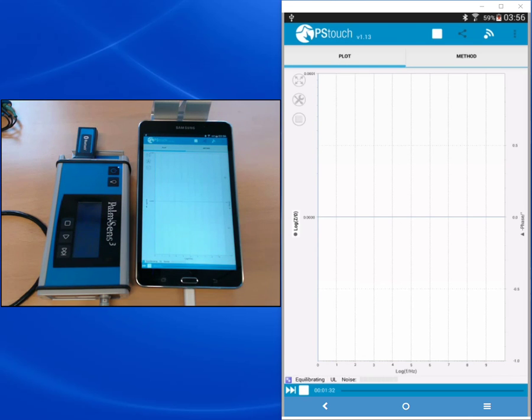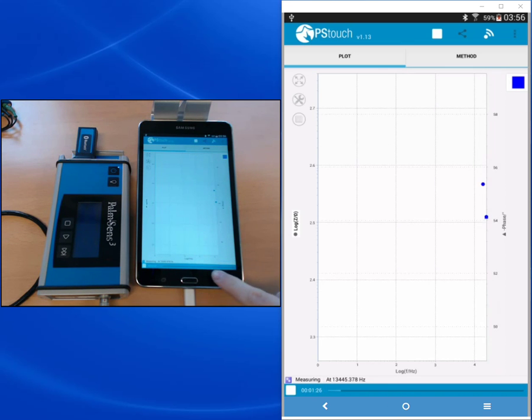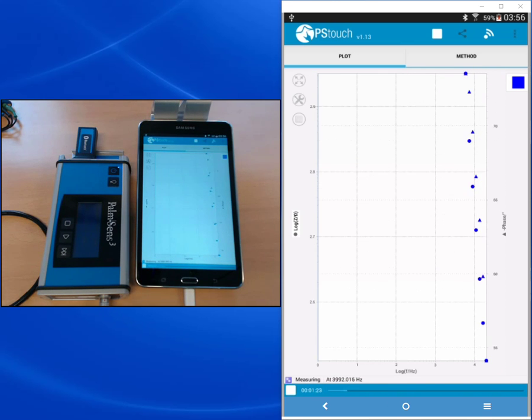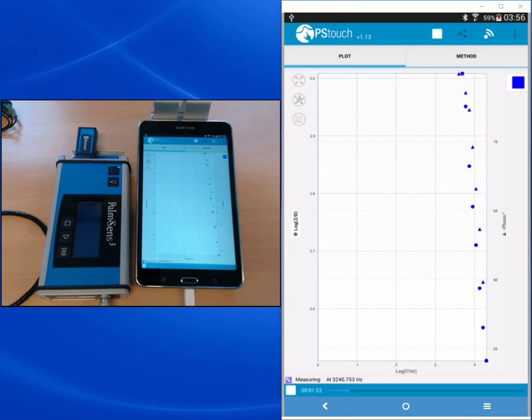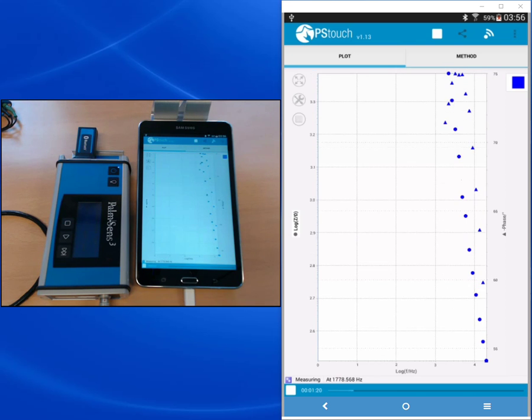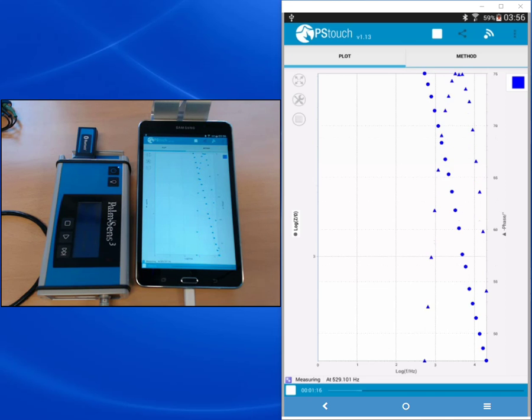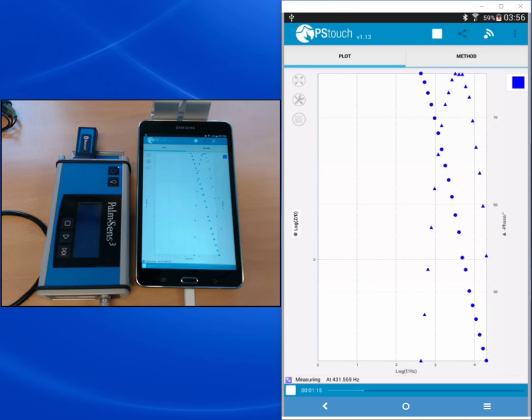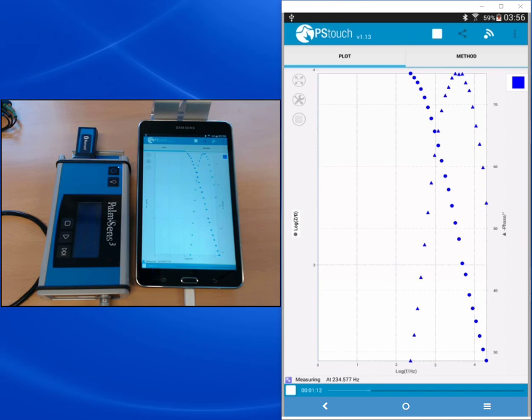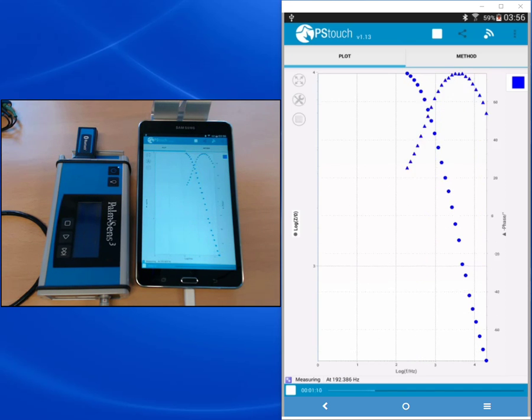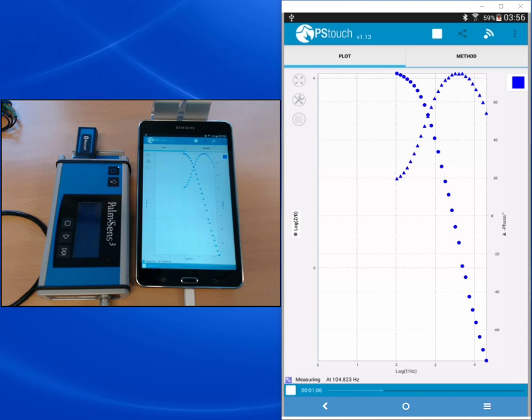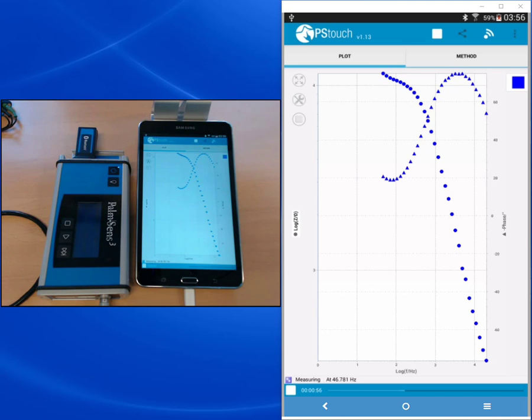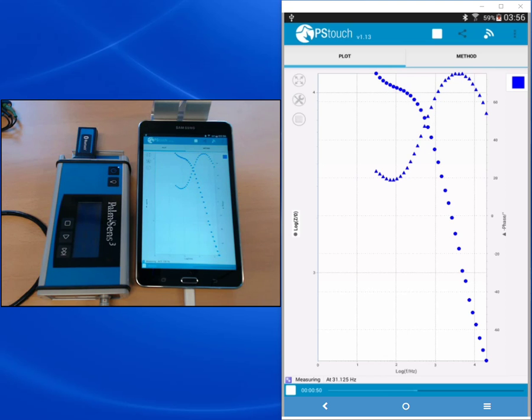We see immediately that the plot window changes. What is the same is we see again the progress bar on the bottom of the screen. But we see that two curves are now plotted in parallel. On the left y-axis you see that the circles are the logarithm of the impedance, and on the right y-axis you see that the triangles are the negative phase. These are both plotted versus the logarithm of the frequency. This is the Bode plot, this is a rather common way of plotting impedance spectra.